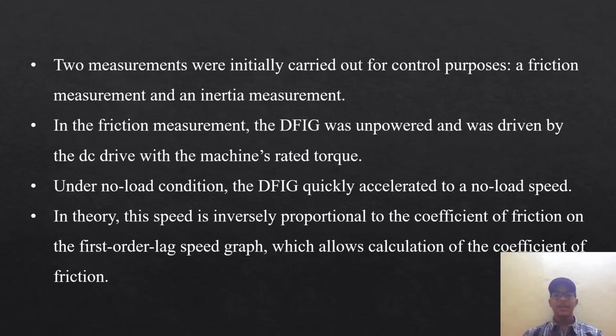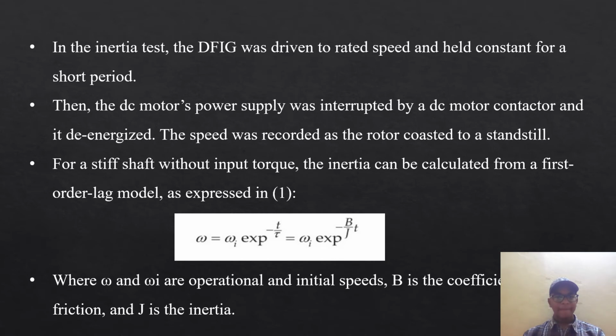Two measurements were initially carried out for control purposes, a friction measurement and an inertia measurement. In the friction measurement, the DFIG was unpowered and was driven by the DC drive with the machine's rated torque. Under no load condition, the DFIG quickly accelerated to no load speed. In theory, this speed is inversely proportional to the coefficient of friction on the first order lag speed graph, which allows the calculation of the coefficient of friction. In the inertia test, the DFIG was taken to the rated speed and held constant for a short period. Then the DC motor's power supply was interrupted and the DC motor was de-energized. The speed was recorded as the rotor coasted to standstill.